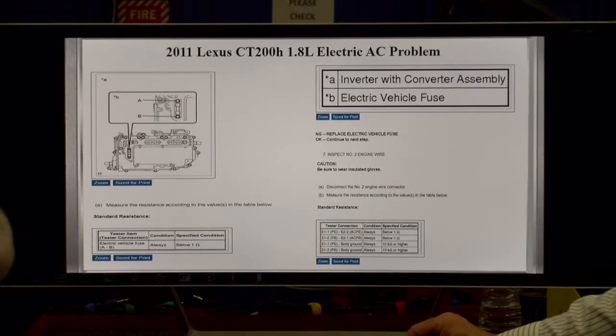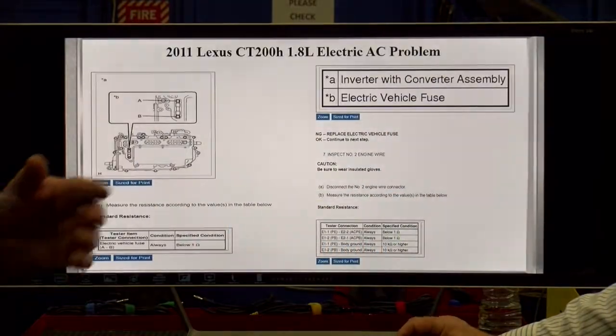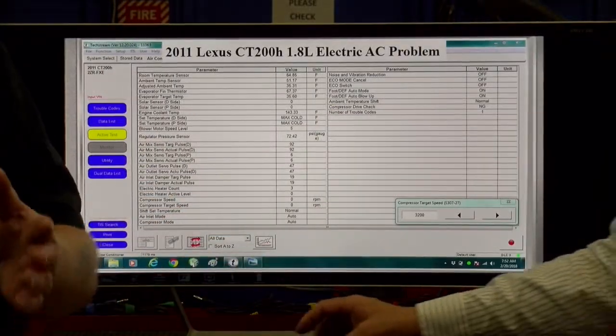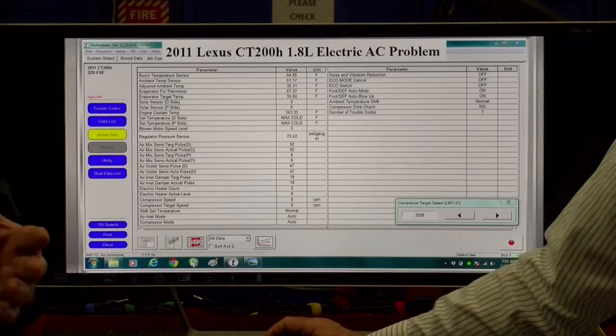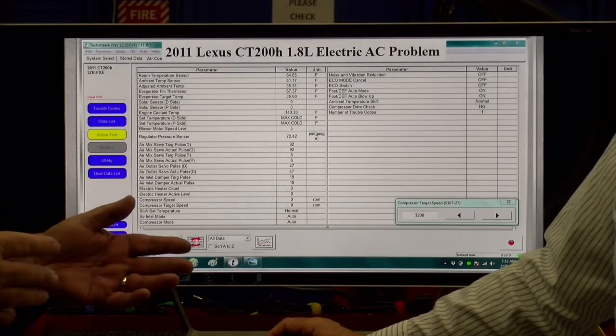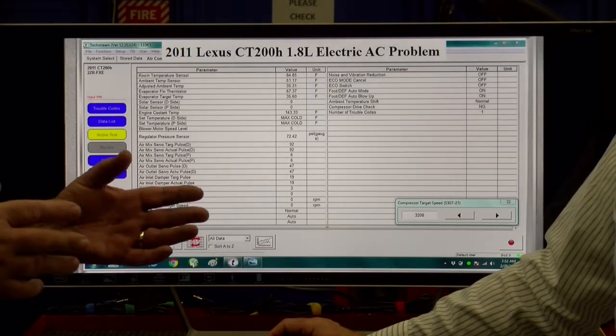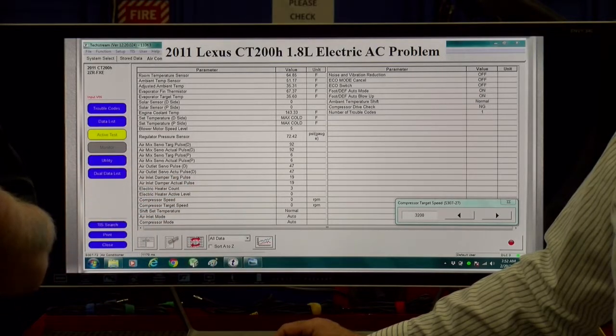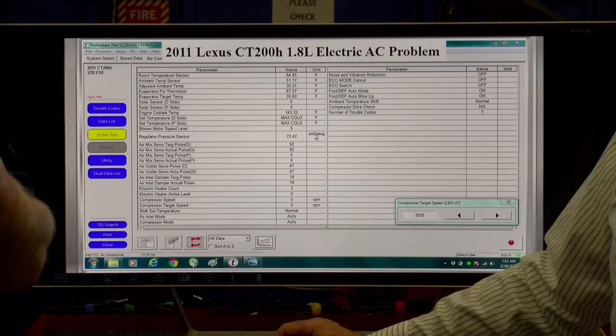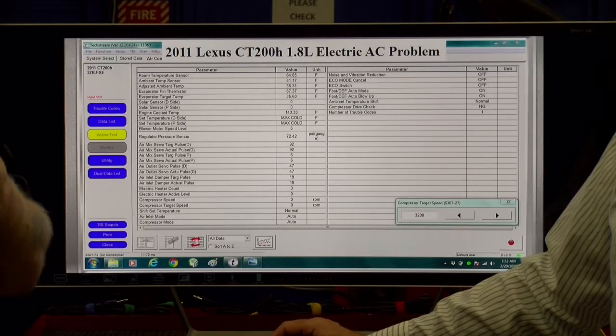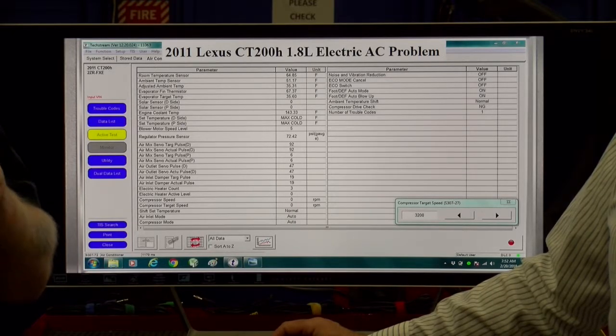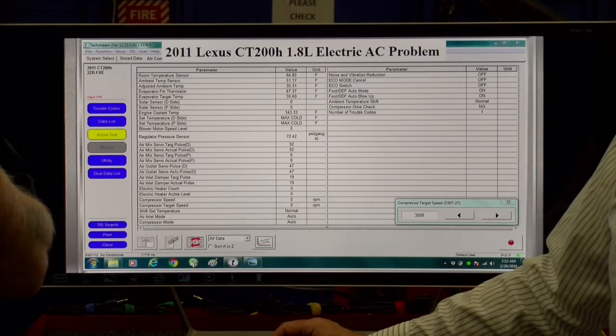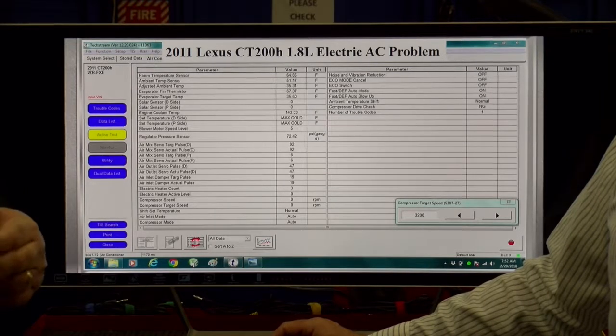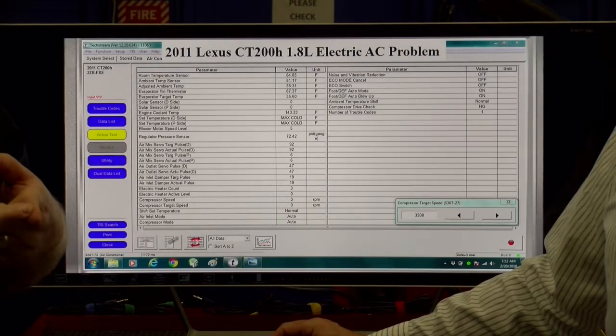I want to interject this too: you heard Gene mention that if you're going to do any measurements on these high voltage systems, you need a meter capable of doing that—Cat 3 or higher, 1,000 volts AC rated. And not just the meter, the leads you're using have to be rated to Cat 3. And wear your gloves when you're doing this, absolutely.